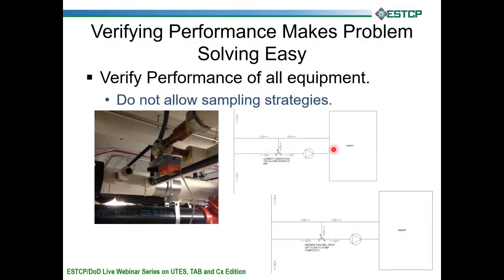And this setup is for a water-to-water heat pump. Typically, they can't receive water any hotter than like 70 degrees in the heating mode. And this is our loop over here. The way we fix that problem is we just put in this mixing valve. So if this water ever gets hotter than 70 degrees, we just shunt some of this colder water, 60 degrees or 55 degree water, here, and it mixes in with our hotter water, and we get the water temperature that we need to the water-to-water heat pump.